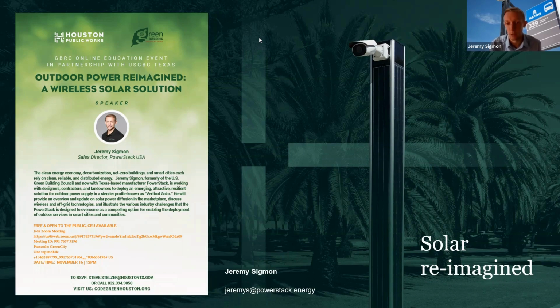Some will say, we're lighting a pathway between our building and our parking lot, and it needs to be on not 24 hours a day, but the full night all the time. And so over the Christmas holiday, it's running full night. That's the darkest time of the year. That's going to be 12 hours or so, maybe from 7 to 7. And so that's just part of the energy model that we would develop together, and that would determine how to manage for that amount of power consumption in the winter months, which is how the whole system is designed, because in the summer or the shoulder months, we'll always have more.